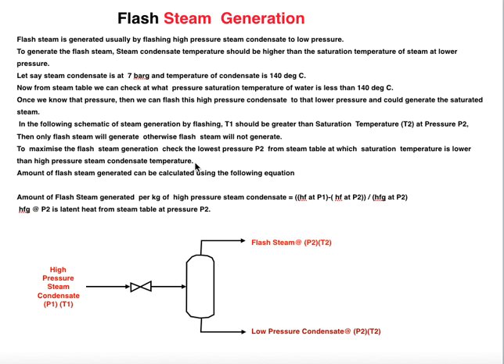The amount of flash steam generated can be calculated using the following equation: [HF(P1) − HF(P2)] / HFG(P2), where HF(P1) is the sensible heat of water at pressure P1, HF(P2) is the sensible heat of water at pressure P2, and HFG(P2) is the latent heat of vaporization at pressure P2. The difference in sensible heat at the two pressures is what drives steam generation.